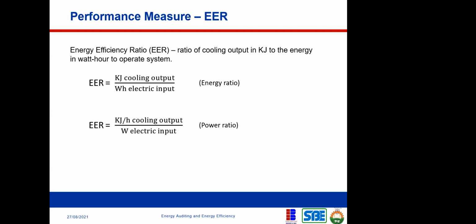Now it is the ratio of cooling output in kilojoule, kilojoule is energy, to the energy in watt hour to operate the system. So in simple formula format, EER is equal to kilojoule cooling output, because the essence of air conditioning is to provide cooling, right? So the cooling output divided by the energy it consumed. The energy, not power. So EER, we can express it in both energy and power. The first one is expressed in the form of energy, while the second one is expressed in the form of power. Okay, so these are just formulas that we should take note of.